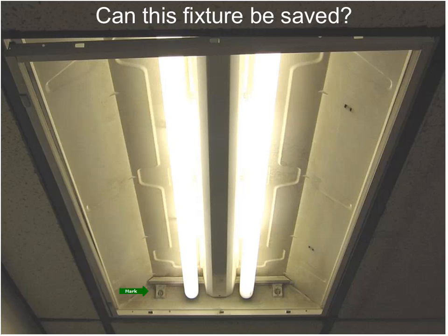And these lamp holders are probably pretty old. They probably need to be replaced. I usually recommend that. You'll see that the housing is discolored. It's not very white, doesn't reflect very well. And this particular troffer has sloped sides, which actually is good. So if this was a really white surface, this would probably not need a new reflector. It'd probably be good all by itself. But this one looks pretty dirty.